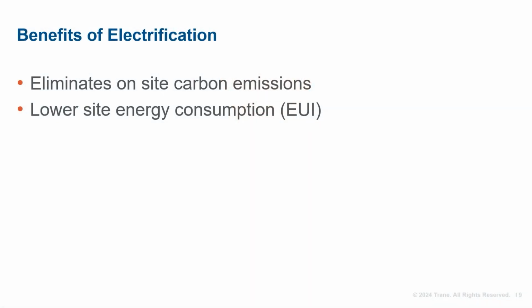The most obvious benefit of electrification is that it eliminates on-site carbon emissions. Depending on the electric grid and the efficiency of the electrified heating system, it may or may not reduce source emissions. Since electrified heating systems commonly have a coefficient of performance, or COP, significantly higher than that of fossil fuel-based systems, they also lower site energy consumption, or energy usage intensity. The last and often most important benefit is that properly designed systems may reduce operating costs. I'll turn it over to Sarah to go over electrified heating design considerations.